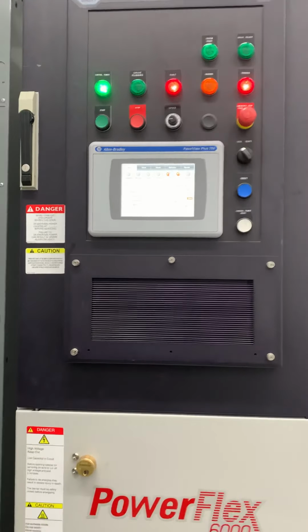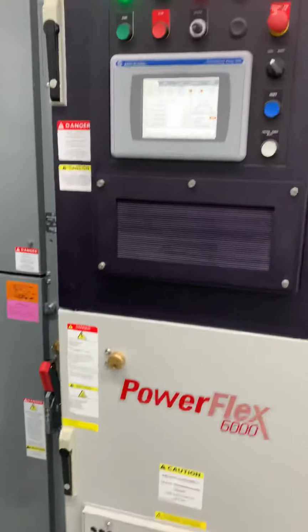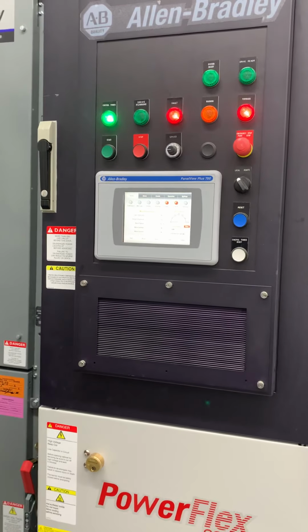Reset. Yeah. So if you look in there now, you'll see what I was talking about with those shutters. The white part of the shutter is gone, and that has slid over, and those knives have gone down and connected to the bus in the back. Gotcha. It's fully automated, with a motor that pulls the contactor in, and you don't even have to be in the building, you can be outside.